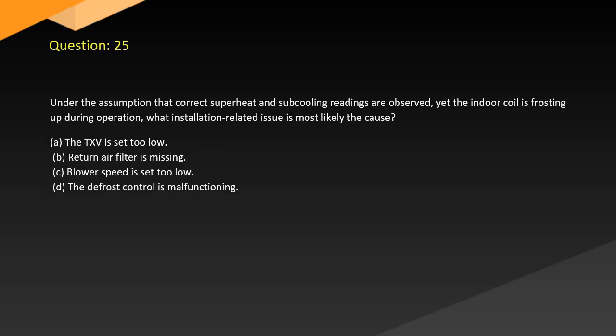Question 25. Under the assumption that correct superheat and subcooling readings are observed, yet the indoor coil is frosting up during operation, what installation-related issue is most likely the cause? A. The TXV is set too low. B. Return air filter is missing. C. Blower speed is set too low. D. The defrost control is malfunctioning.